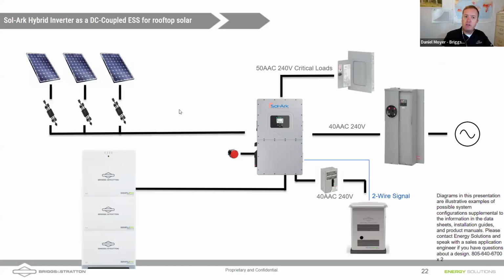DC coupled, right? The idea here is that we're bringing DC down. These are APsmart rapid shutdown devices. These ones, I should change my picture. These ones are meant for 2 modules each, but they sell one for 1 module each. We're bringing that into our MPPTs, down the MPPTs into our battery. We have our backfed breaker still over here, and then we're able to bring our 50 amps up here for our critical load subpanel. We do have a 2-wire signal to start, and you don't necessarily need a breaker here because the generator has the built-in breaker, but some code AHJs might want you to put in an additional breaker.